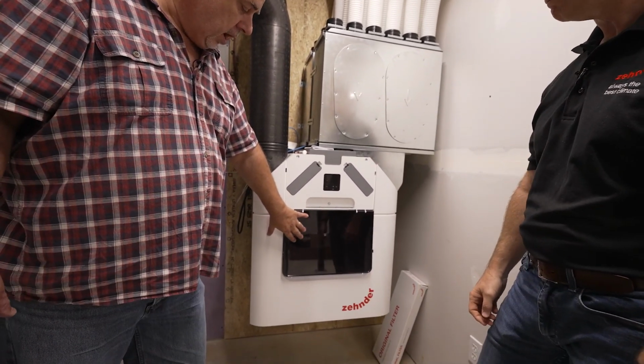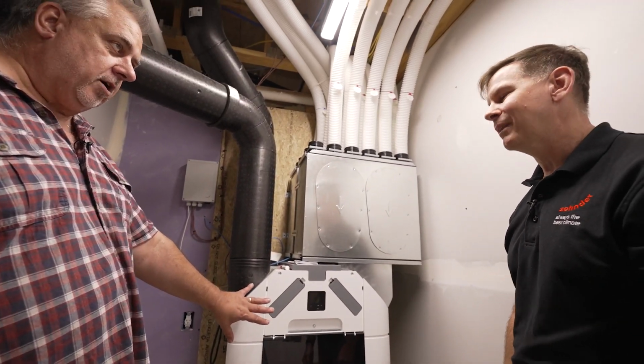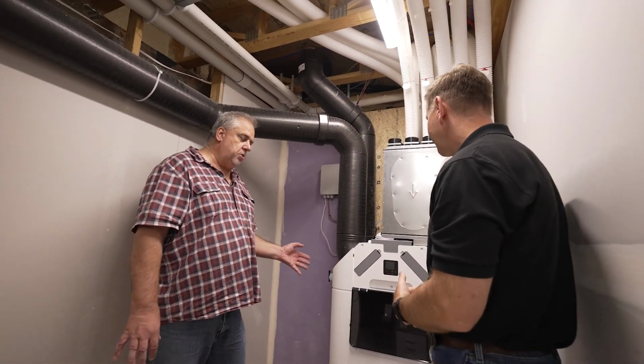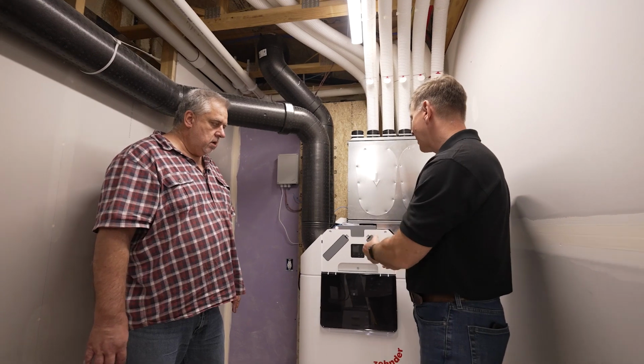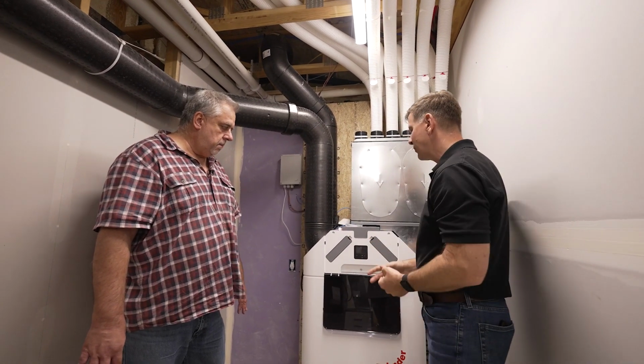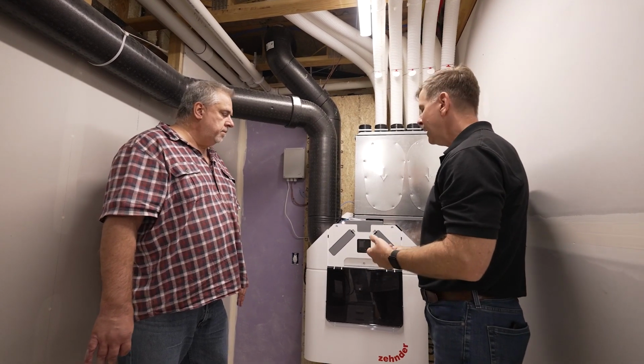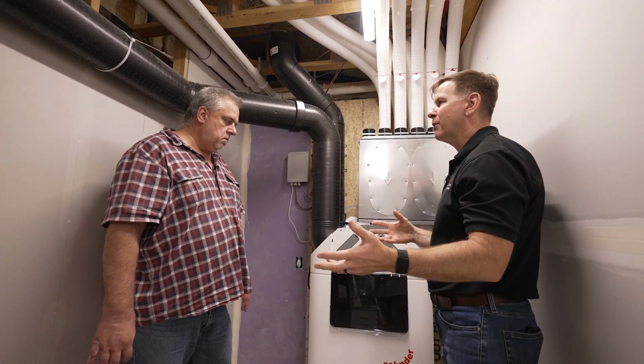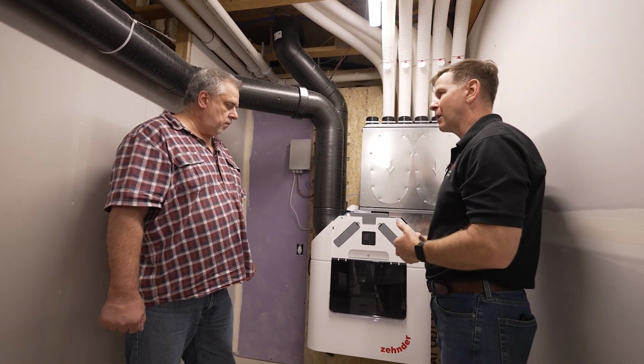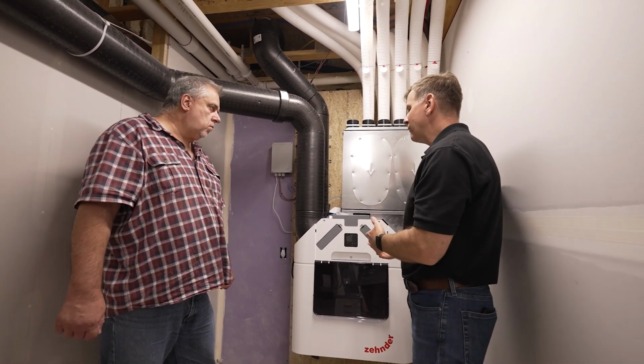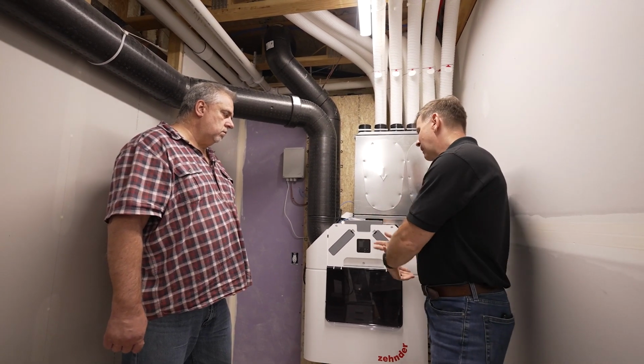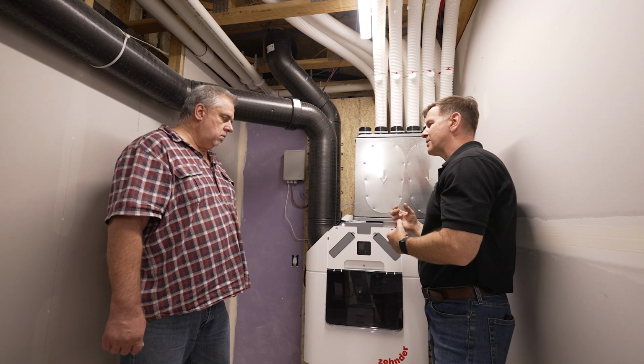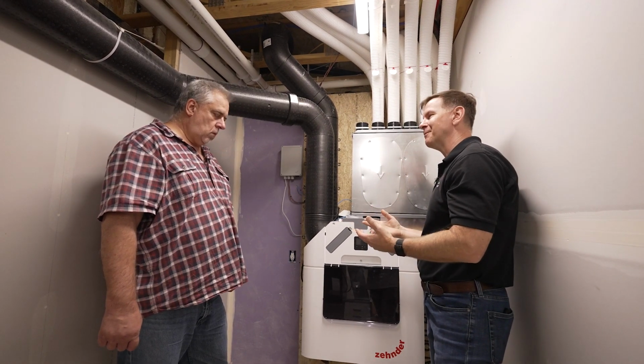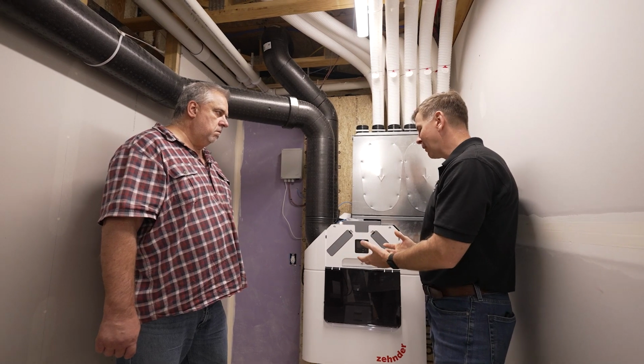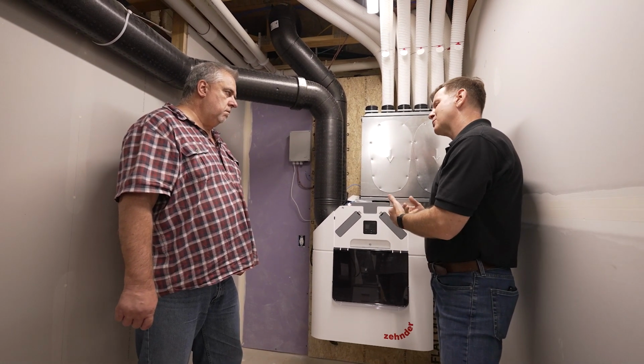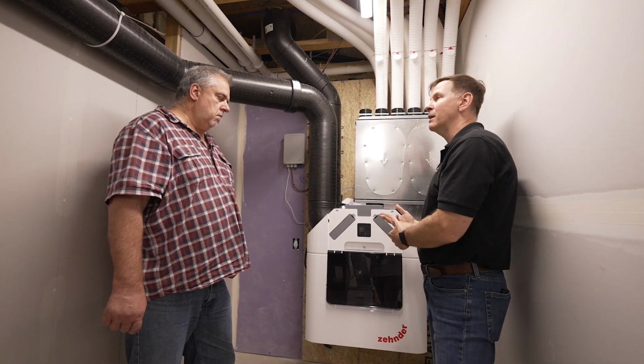But you said it's going to pass through the core. Now, we have some options in that core, right? Yeah. And what are the options? Why would I choose one over the other? Yeah. All of Zehnder's units will look the same on the outside, but you can order them either as an HRV or an ERV. HRV is commonly called heat recovery ventilator. ERV is commonly called energy recovery ventilator. And the difference is the heat recovery ventilator transfers heat across the membranes between the 2 air streams. And it's the kind of heat that we normally think of with heat. It's sensible heat. Right. ERV, or energy recovery ventilator, is going to be able to transfer both that sensible heat and latent heat, or what we call humidity.